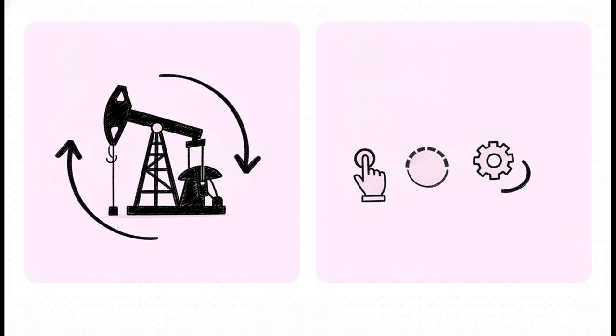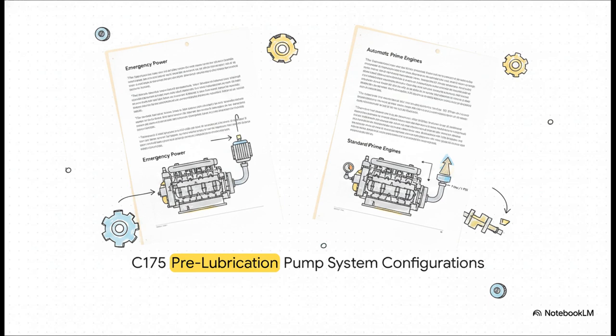On the flip side, we've got the automatic pre-lube system, and this is for prime power. It stays completely quiet until a planned start, runs just long enough to sense adequate pressure, and then it allows cranking. So here, you're trading a few seconds of delay to save on pump wear over the long haul. Looking at this setup, the documentation is super clear. A relatively small population of engines, the ones strictly for emergency power, ship with that continuous pre-lube pump. But standard prime engines, the vast majority of them, use the automatic system. That gives the engine just enough time to build pressure up to roughly 7 kilopascals, or about 1 psi, right before the starter actually engages.